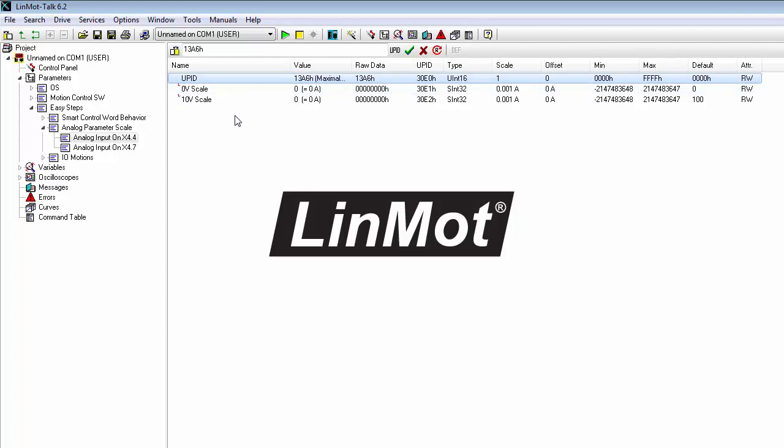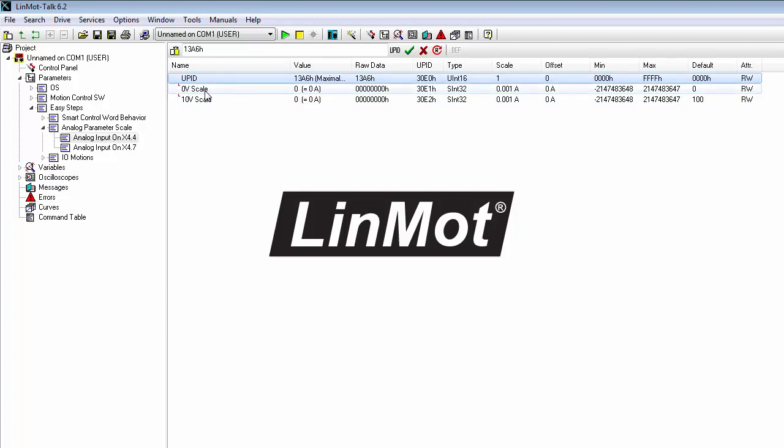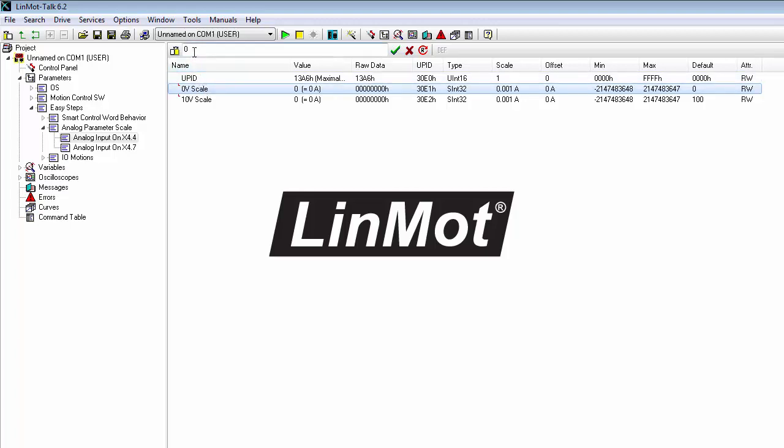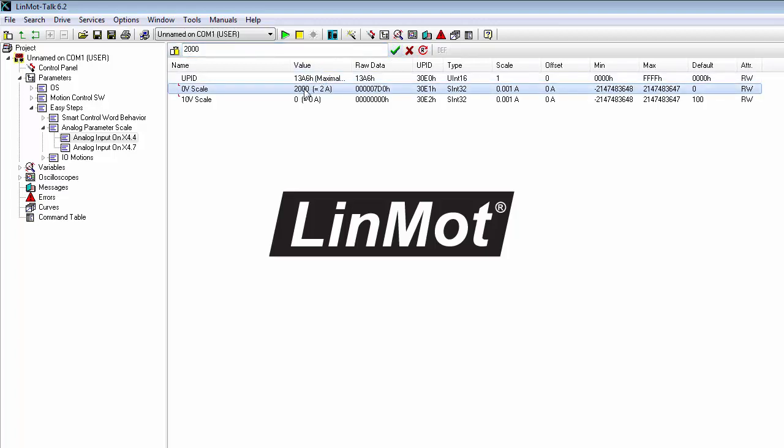The next thing we have to do is adjust the scaling. So basically, this is maximal current. What current do we want it to be when the signal is 0 volts? And we'll make that 2 amps. So we go up here and put in 2, but we have to put in 2000 to get the scale right. We click our green checkbox and that 2000 equals 2 amps.